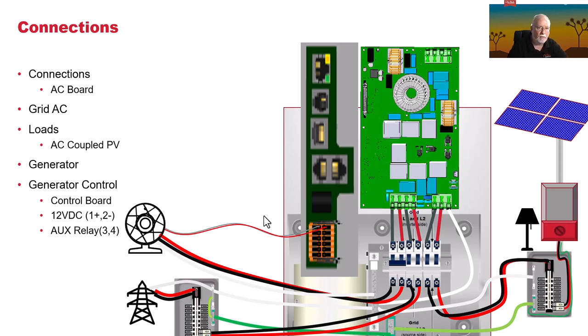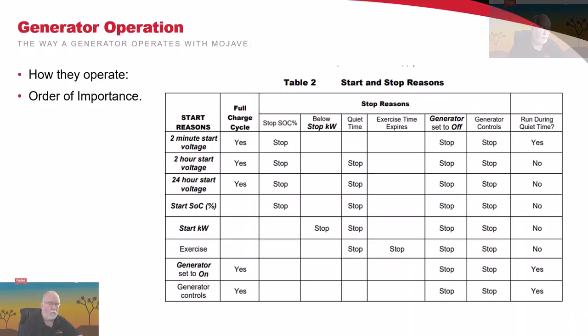The top 2, 1 and 2, are a 12 volt DC option. They are polarity sensitive, so make sure you get that correct if you have a DC driven unit. And then 3 and 4 are the auxiliary relays. When that auxiliary relay is put in place and closed, the generator starts, the AC board flips over to the generator, everything's fine. We here at Outback work with generators off-grid all the time.